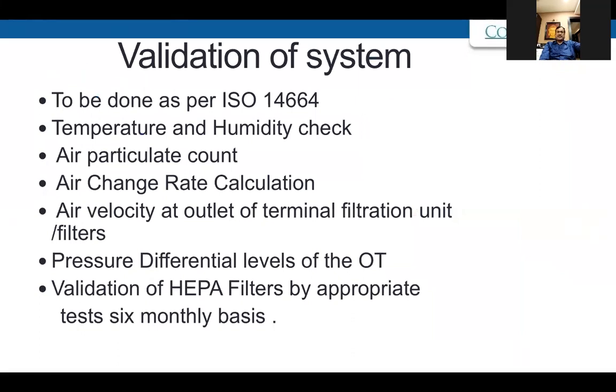So validation of the system is more important for us from the point of view of NABH accreditation as well as various other accreditations. It has to be done as per ISO standards. Temperature, humidity has to be checked. Air particulate count has to be checked. Air change rate. This is all done most of the time by the vendors. So vendors are now well trained because of NABH's presence for such a long time. Every vendor is, I think, trained to do it appropriately.